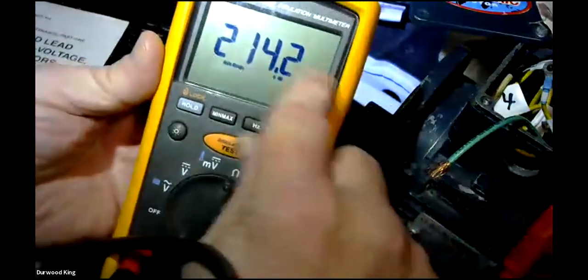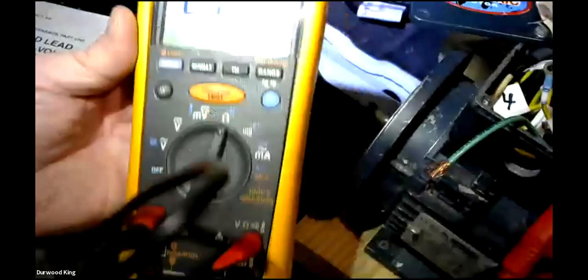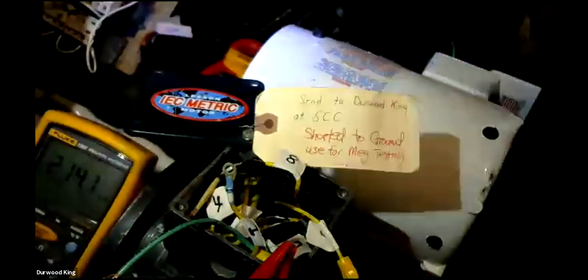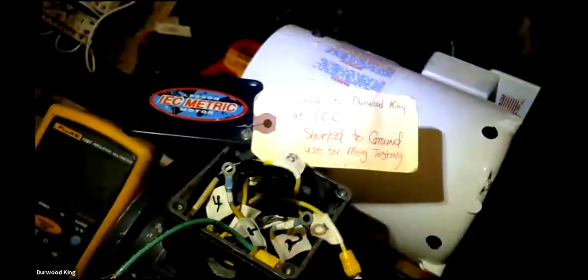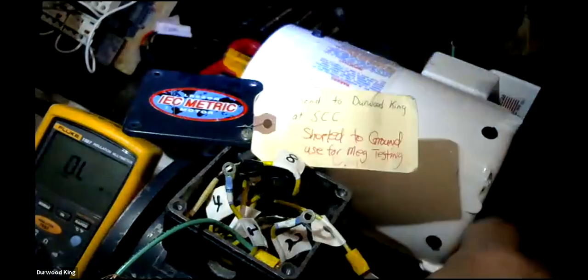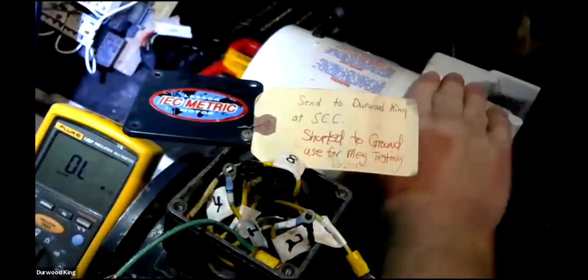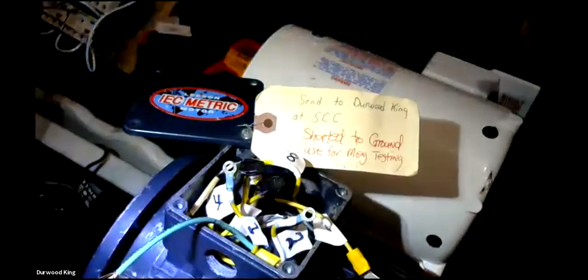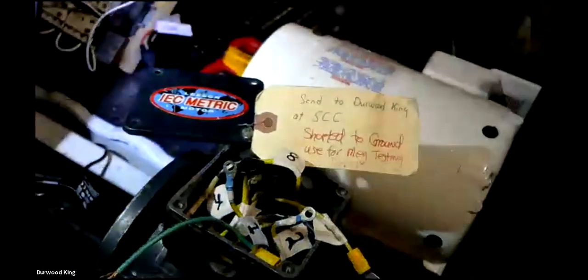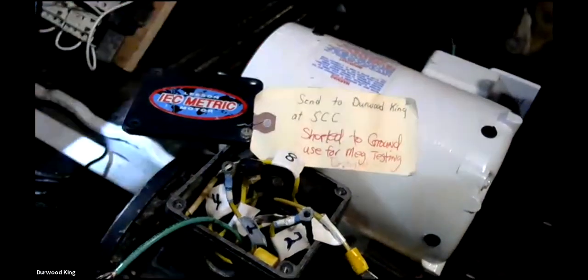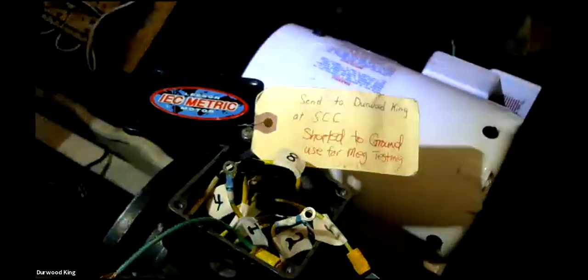So, Victor, does that help seeing that? Yes, sir. So you had an extremely bad motor. That's why they tagged that thing, and they put on there to bring it to me at this school, because it's one of them motors. It's a classic that it is horribly bad. Let's flip it around and do a resistance reading through this one, and you'll see that this is a healthy motor over here. And it'll be obvious when you get the resistance readings that they will be balanced, that it's a healthy motor. So let's flip this around.